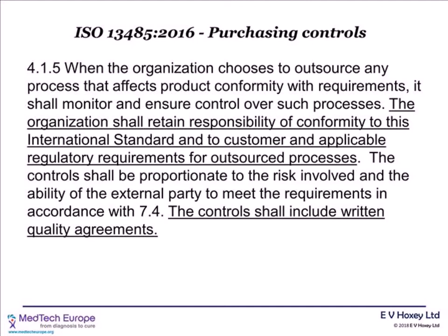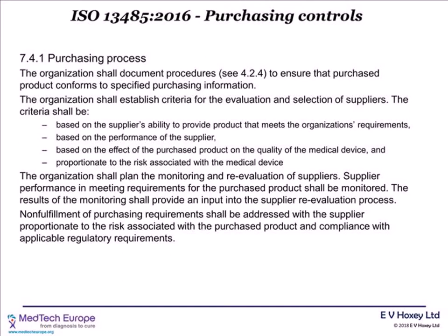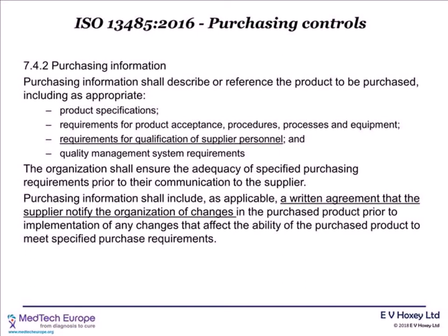The purchasing controls section has been reorganised to try and make it a bit more logical in terms of its flow of evaluating and selecting suppliers, monitoring their performance, and re-evaluating suppliers in a kind of systematic order. And it really gives you some criteria here for a risk-based approach, whereby you put greater emphasis on suppliers of processes or products which have a greater risk to the safety and performance of the device or to meeting regulatory requirements. In terms of the purchasing information, when there's a need to specify details of how personnel at the suppliers' organisations need to be qualified, then that's detailed, and a requirement to have a written agreement of changes from the supplier if they make changes to their product or process.